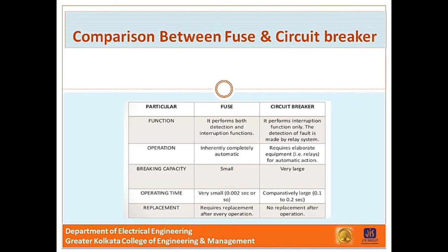Now high rupturing capacity fuses can be rated to safely interrupt up to 3 lakh amperes at 600 volts AC. Special current limiting fuses are applied ahead of some molded case breakers to protect the breakers in low voltage power circuits with high short circuit levels. Now current limiting fuses operate so quickly that they limit the total let-through energy that passes into the circuit, helping to protect downstream equipment from damage. Now these fuses open in less than 1 cycle of the AC power frequency, and a circuit breaker cannot match this speed.